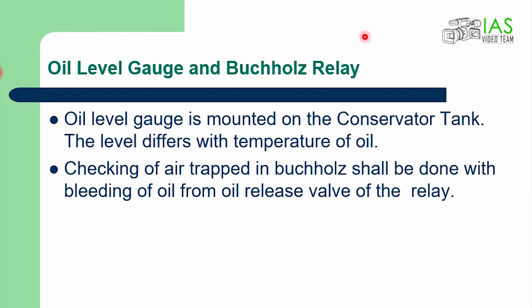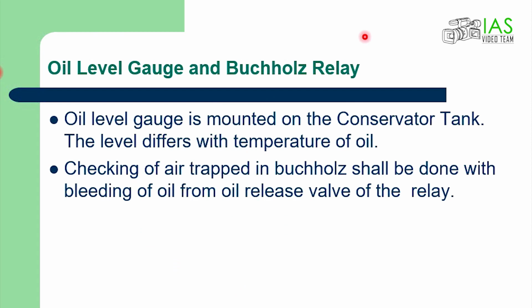Oil level gauge and Buchholz relay, yeah, these two we have already discussed. And overfilling, you remember this, overfilling may cause bleeding of oil through the breather. The oil can come through the breather. Yeah, this we have discussed. If the Buchholz relay collected gas is combustible, what happens?